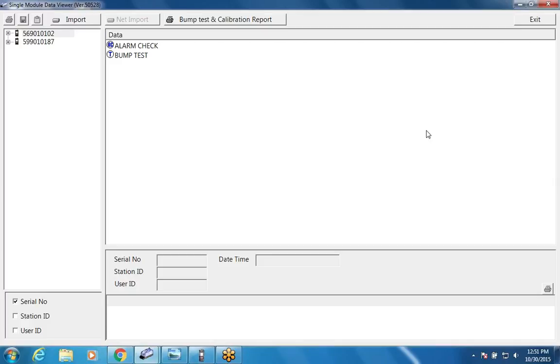So what I'm going to do now, I'm going to go ahead and do a bump test. If you look at my bump test configuration, I do have the alarm check turned on, and now I'm going to turn on the auto print also, so it'll print out the results of my bump check. So now I'm back to the main screen. This is where I can tell it to do a bump or do a cal or do an alarm check. So I'm going to go ahead and hit bump. And it tells you what's happening in the status bar at the top. It says I'm flushing with air right now. So Bruce, now I'm applying the gas.